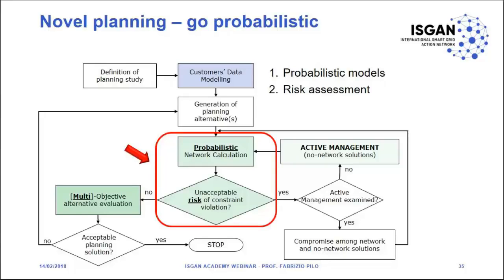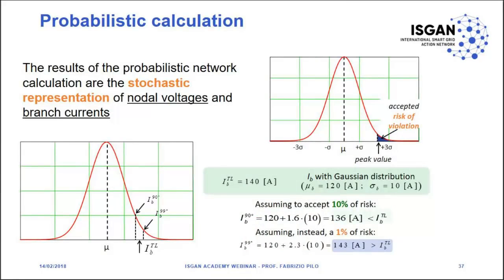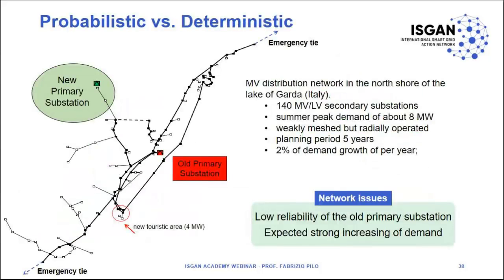Another important point is probabilistic calculation. There are different ways to approach probabilistic models: we can use probabilistic load flow, Monte Carlo simulation, or fuzzy set theory. What is really important is that we can manage risk in an objective way. Establishing the level of acceptable risk is not easy, but we can define it in advance. This is a real example from Italy: a distribution network at Lake Garda with 140 medium-voltage to low-voltage secondary substations, a demand of about 8 megawatts, a weakly meshed but radially operated network, and a 5-year planning period with 2% per year demand growth.